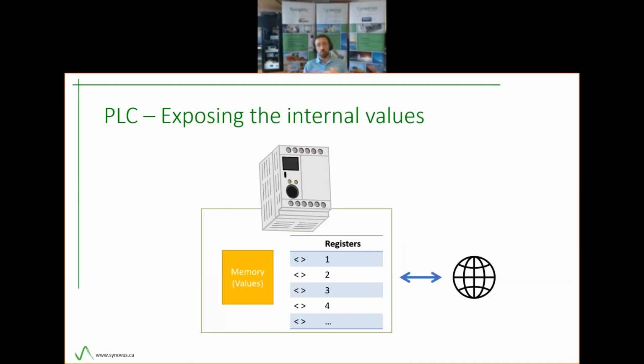Rather than sending human readable commands and receiving human readable values, all of these are based on some form of values in memory, exposed through a table of registers with addresses. One of the simplest protocols we really like to use is Modbus—it's widely supported, pretty simple, yet efficient.